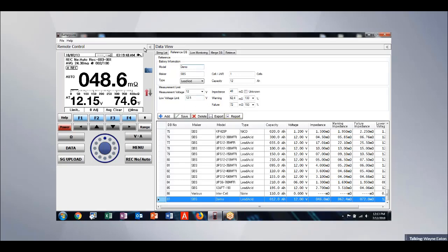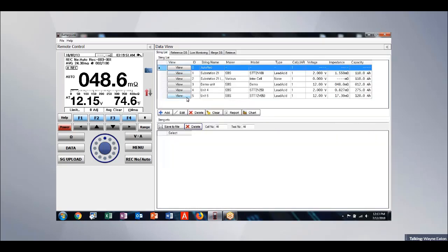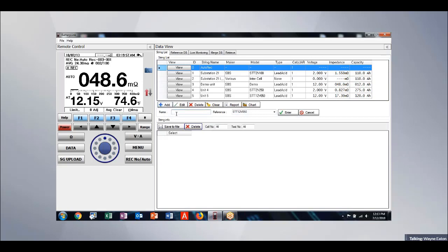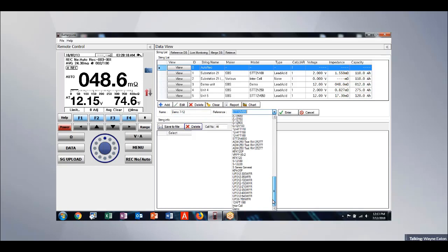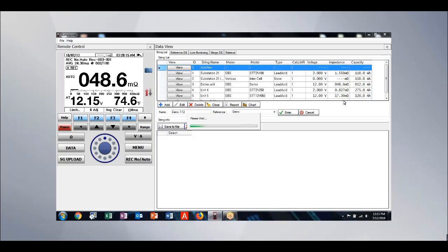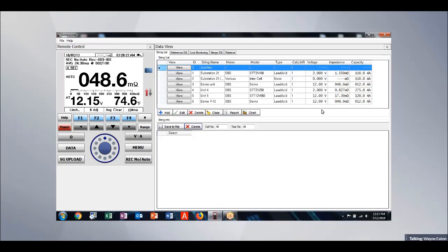Once it updates that data, you'll get an audible confirmation, and then we can go over to string list. We're going to add a new measurement location. And for today, we're just going to call it demo 711. That's the 12th, 712. Then we come over to that reference database. We find our reference value that we just entered. And we're going to add that new string into the top of the software. On the unit itself, it's going to set apart memory blocks to record 100 historical readings for that cell.